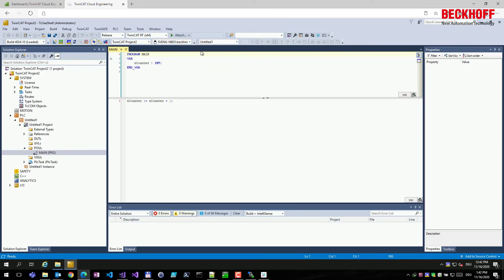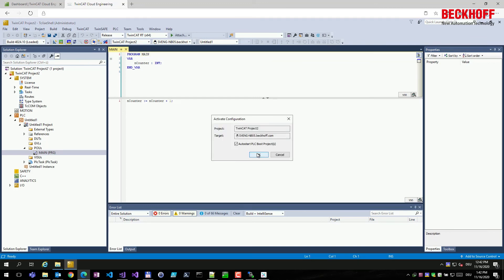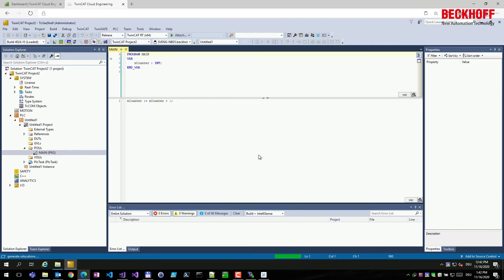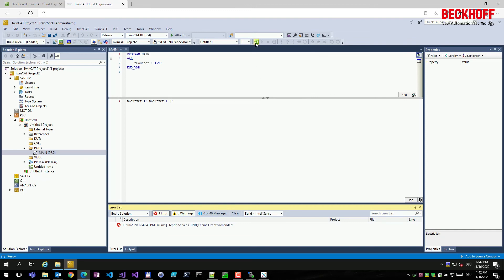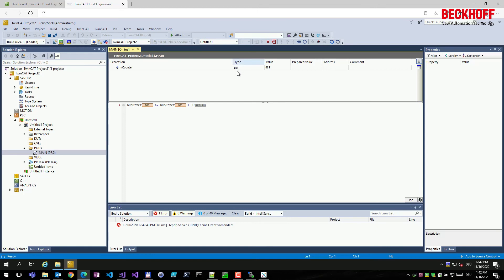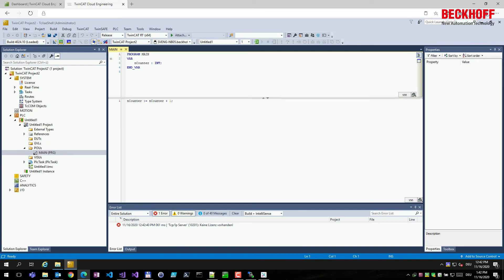After saving the configuration file, TwinCAT is restarted so the new configuration is loaded and the ADS over MQTT route is established to the TwinCAT Cloud Engineering instance. Switching back to the web browser and the remote desktop session, TwinCAT XAE now shows a new physical hardware device — with a secure connection symbol. We select the device and deploy the TwinCAT automation project to physical hardware using the regular workflow: connect to target, activate configuration, download configuration, then log into the PLC application for debugging and monitoring.